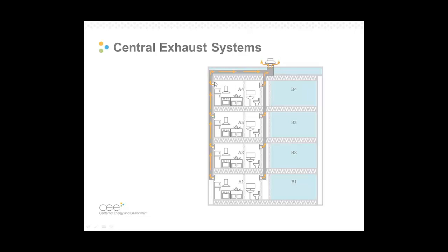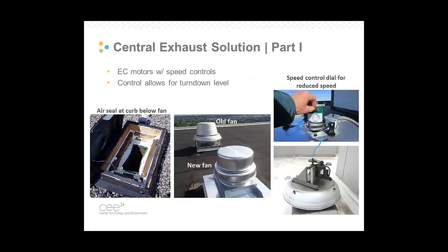Now I'm going to move to exhaust systems. When you're retrofitting exhaust systems, there are really two parts to it. You're changing out the fan here at the rooftop in most cases for reduced exhaust flow, and then you're dealing with the inlets. There are balancing devices typically at each inlet, and there's a recommendation that we have for that to maintain balanced flow from top to bottom of the duct or the shaft.